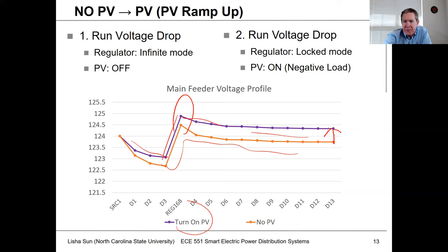What we'd be looking at is what's the percent change in this voltage, what's the delta with respect to nominal voltage? This is where we would look to see if this is going above our restriction. A lot of utilities would maybe use numbers like 2 to 2.5% or 3%. Basically, the larger this PV plant is, the more this change is going to be. The other thing that's going to impact this change is the electrical distance between the substation and the PV. The longer that electrical distance, the more the change is going to be.